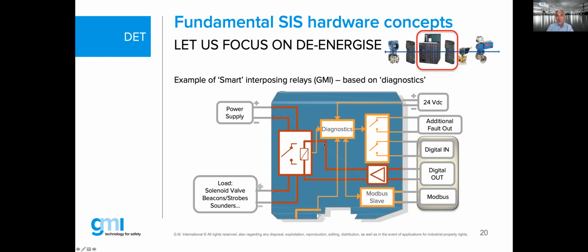And if for some reason what the relay is trying to send out is not what is being measured back as feedback signals, that will be alerted into a diagnostic message, which they show over here in this example, which is the picture I show you here, which we call a smart interposing relay. They can feed this signal back to your control platform.